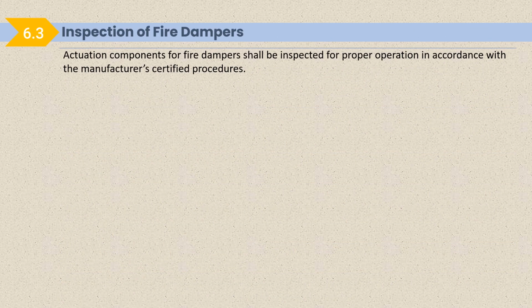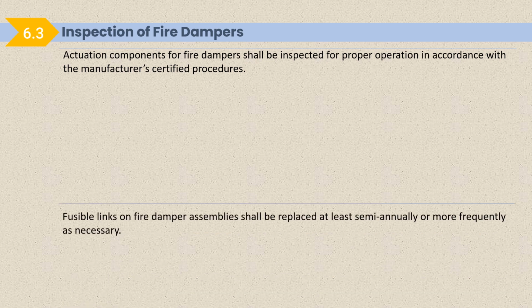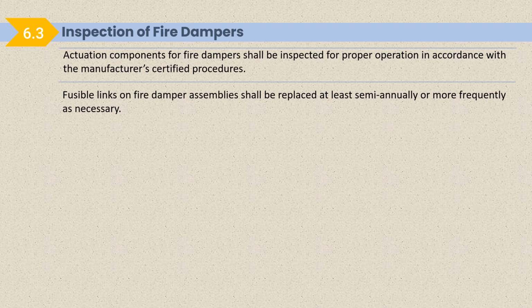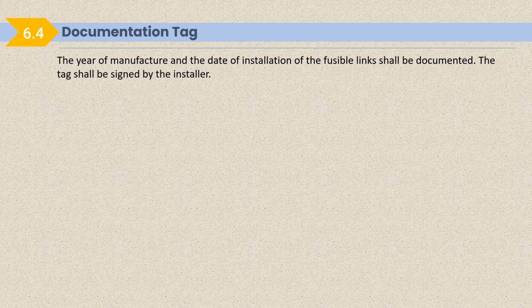Inspection of fire damper. Actuation components of fire dampers shall be inspected for proper operation in accordance with the manufacturer's certified procedure. Fusible links on fire damper assemblies shall be replaced at least semi-annually or more frequently as necessary. Documentation tag: this is also given as a requirement. The year of manufacture and the date of installation of fusible links shall be documented. The tags shall be signed by the installer.